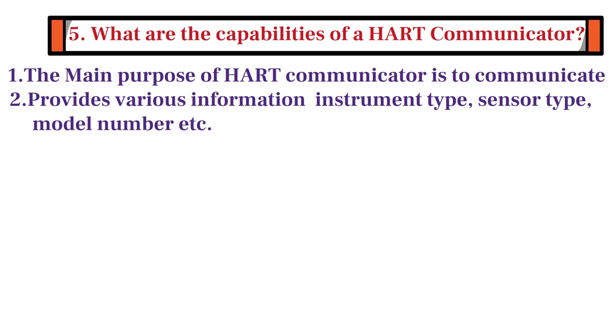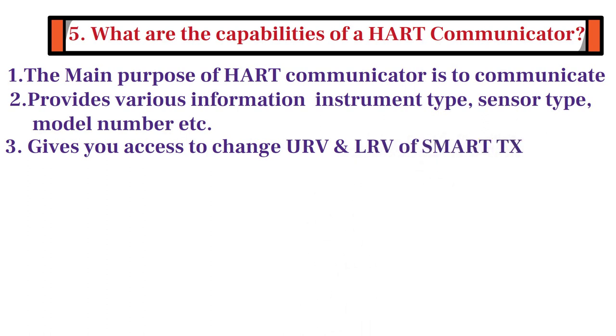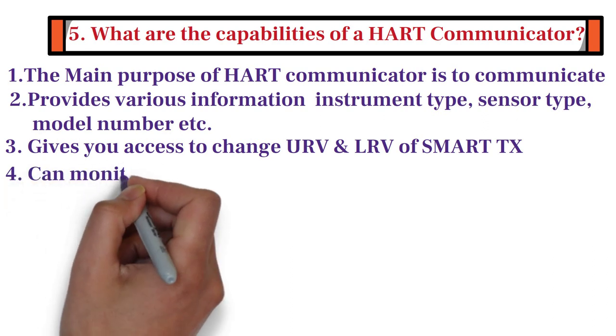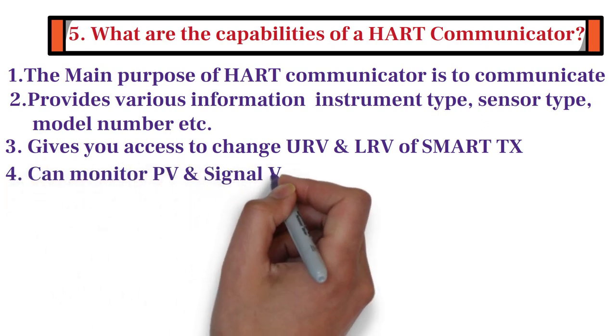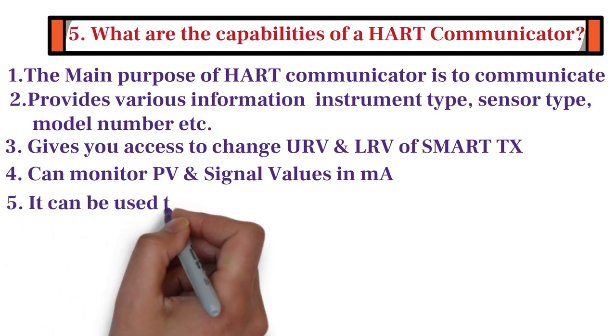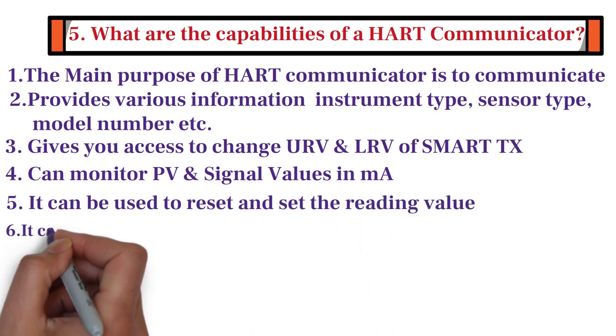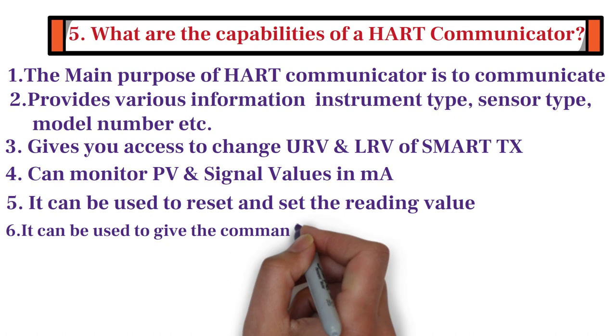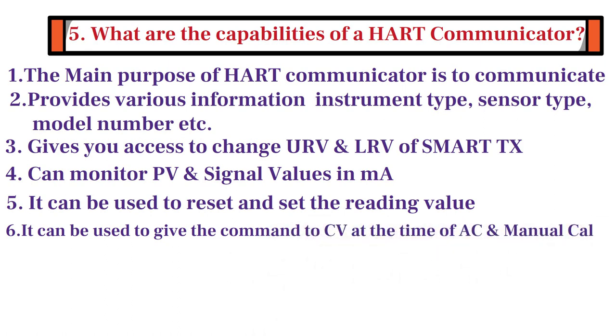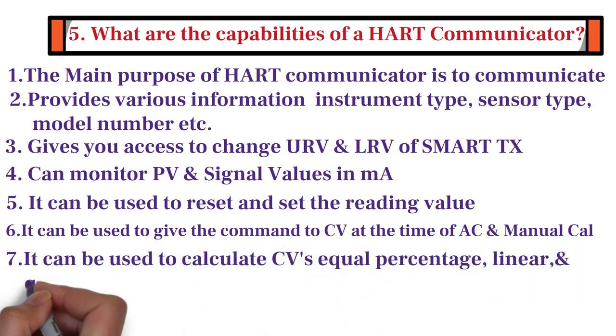Third capability is that HART gives you access to change upper range value and lower range value of smart transmitter. In addition to this, with the help of HART communicator, you can monitor process variable and signal values in milliamps. HART communicator can also be used to reset and set the reading value. Furthermore, HART communicator can also be used to give the command to control valve at the time of auto and manual calibration. Last but not the least, it can also be used to calculate control valve's equal percentage, linear, and quick opening.